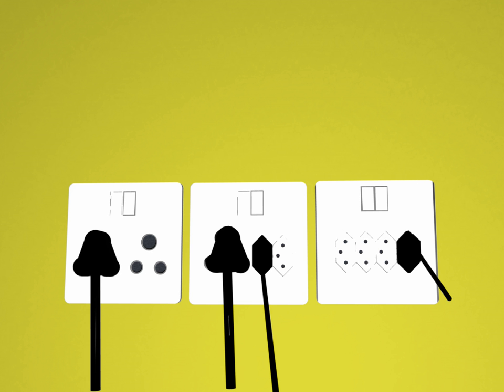Whereas IEC 60906-1 specifies a single 16A rating with 4.5mm pins, NBR 14136 has both 10A and 20A ratings. The 10A plug has a pin diameter of 4mm, and the 20A plug is 4.8mm.